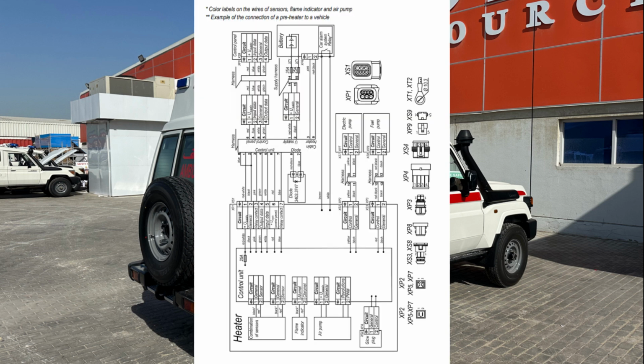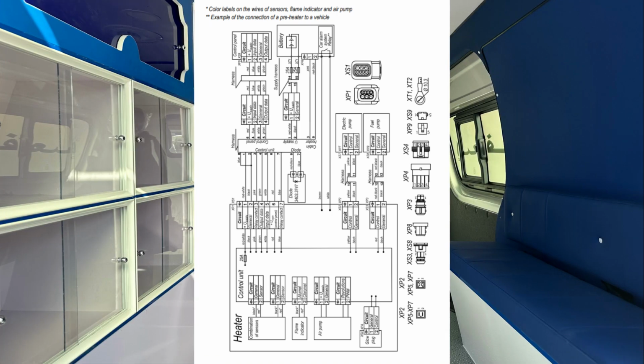Automatic control features. 1. If for some reason the heater did not start, the startup process will be automatically repeated. After 2 failed attempts, the heater will be switched off. 2. If burning is interrupted during heater operation, the heater automatically restarts. Restarts after consecutive flameouts are performed up to 3 times.